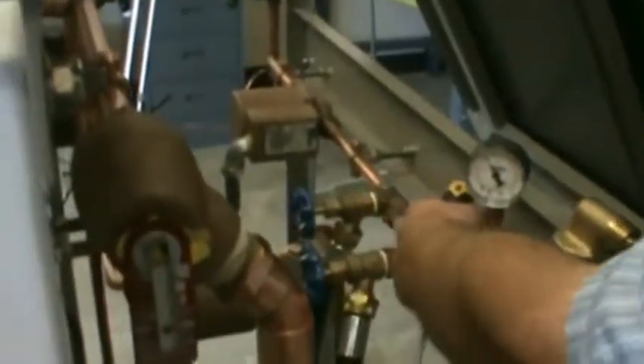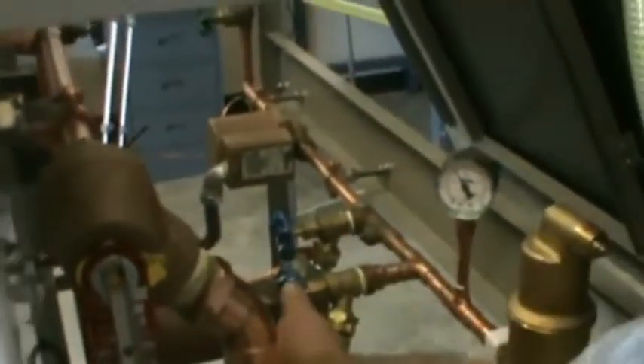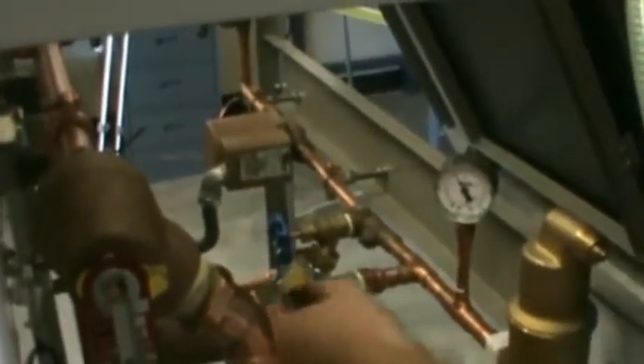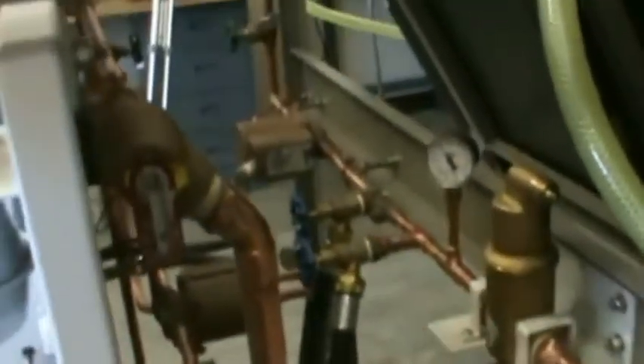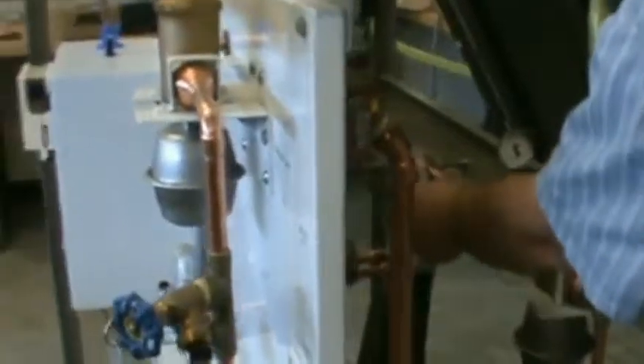Here's the procedure that we did: we first opened the return valve all the way, we shut the flow valve, and then we gently opened this. The things that we had was over-pressure in there, so we don't want to exceed 15 psi.